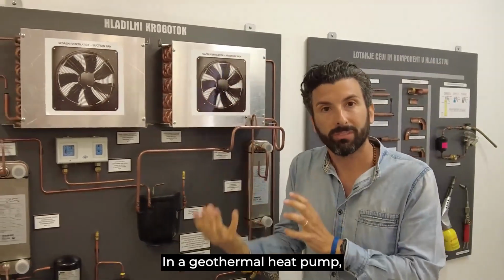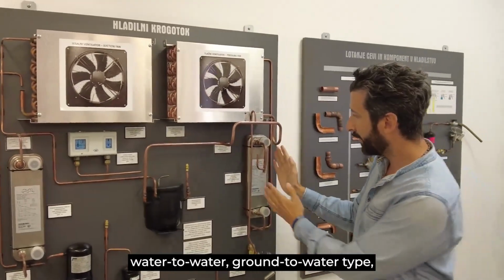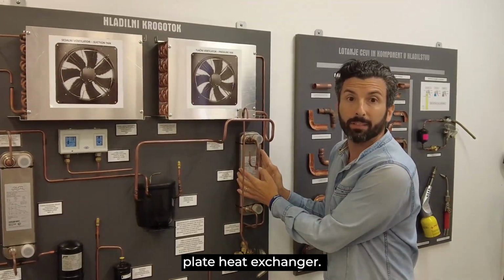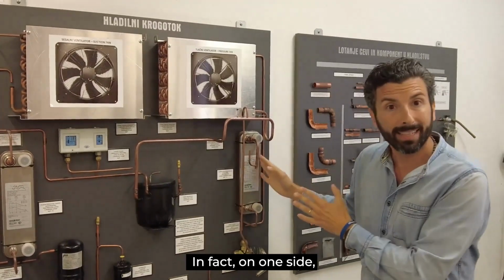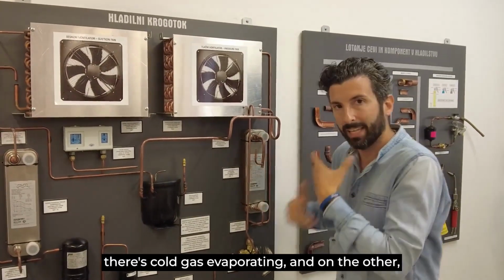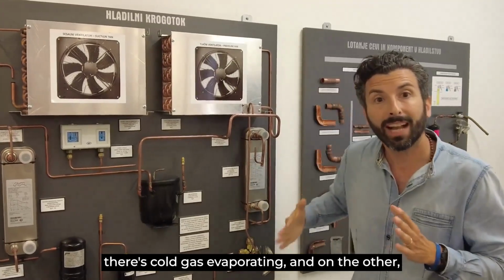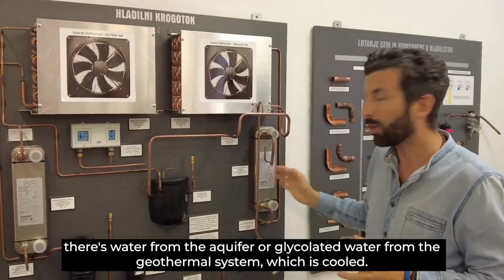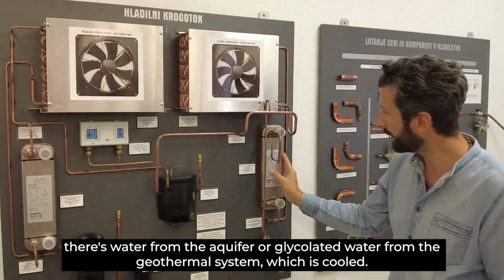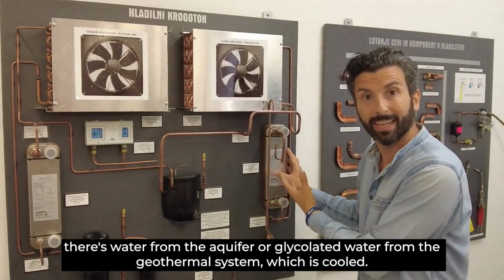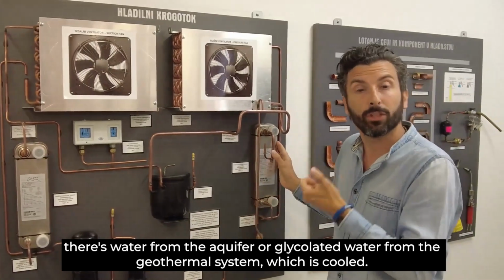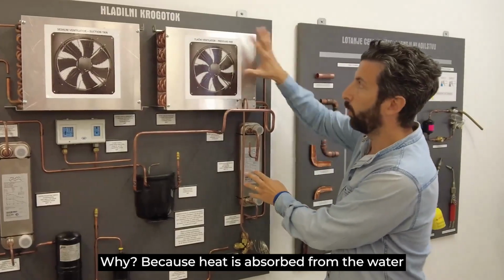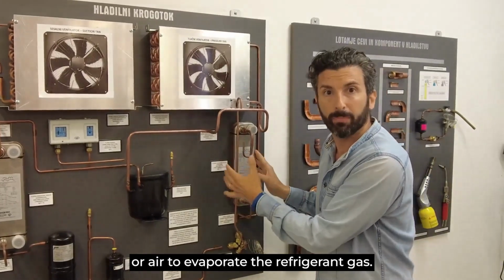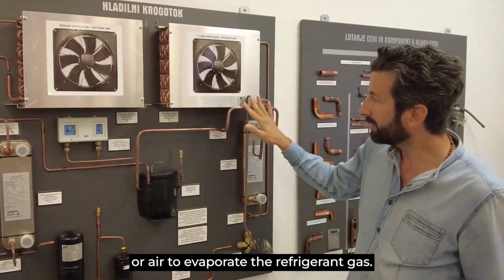In a geothermal heat pump, water-to-water, ground-to-water type, you will find the evaporator as a plate heat exchanger. On one side, there's the cold gas evaporating, and on the other, there's water from the aquifer or glycolated water from the geothermal system, which is cooled. Why? Because heat is absorbed from the water or air to evaporate the refrigerant gas.